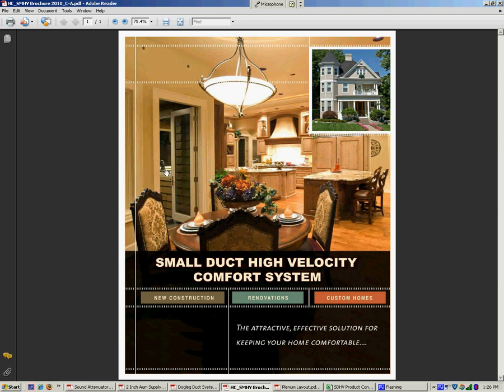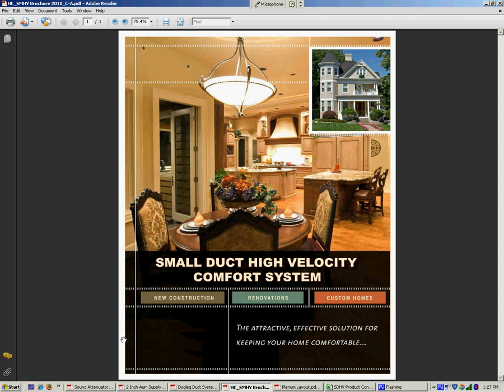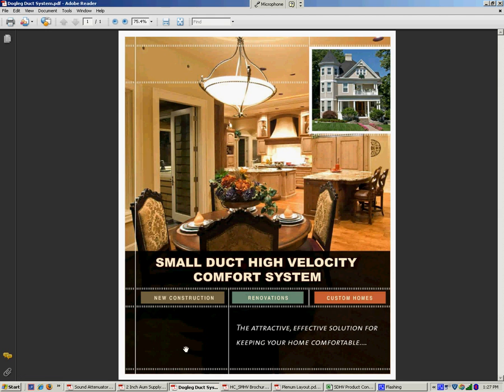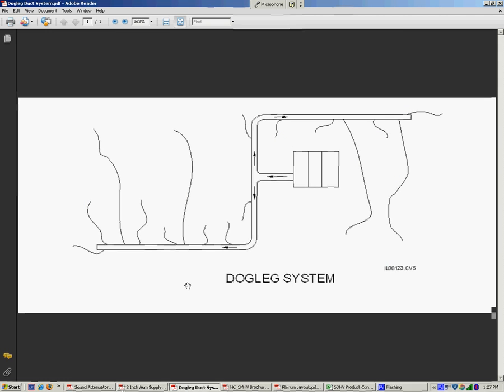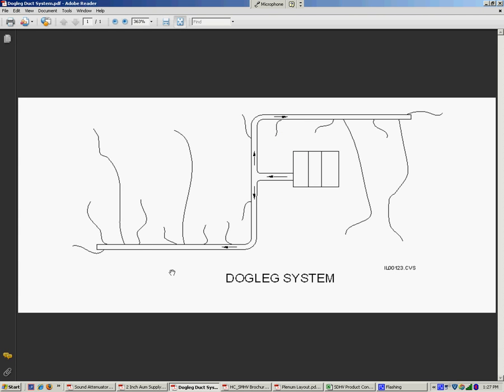Now, the first consideration when we're doing a small duct system is the plenum layout. And the I&O manual is going to help you decide what's the best layout for your particular job - horseshoe, perimeter, H-pattern, etc. So once we've determined that, we need to figure out what is the distance between the plenum and the actual outlet of the register. It's going to have a significant impact on the CFM output of each one of the registers.